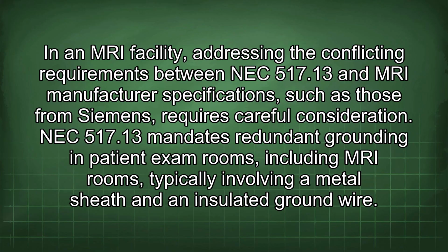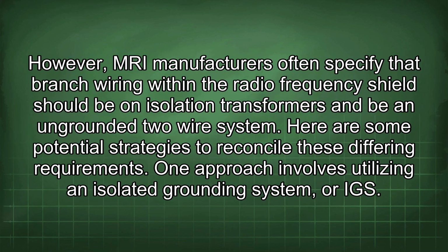In an MRI facility, addressing the conflicting requirements between NEC 517.13 and MRI manufacturer specifications, such as those from Siemens, requires careful consideration. NEC 517.13 mandates redundant grounding in patient exam rooms, including MRI rooms, typically involving a metal sheath and an insulated ground wire. However, MRI manufacturers often specify that branch wiring within the radio frequency shield should be on isolation transformers and be an ungrounded two-wire system.